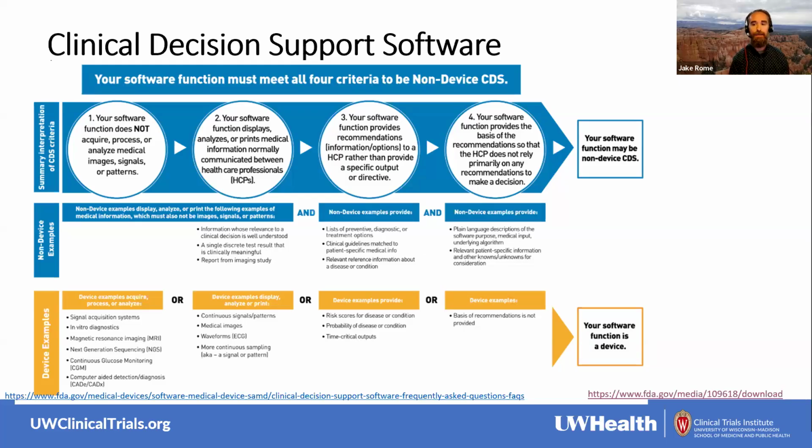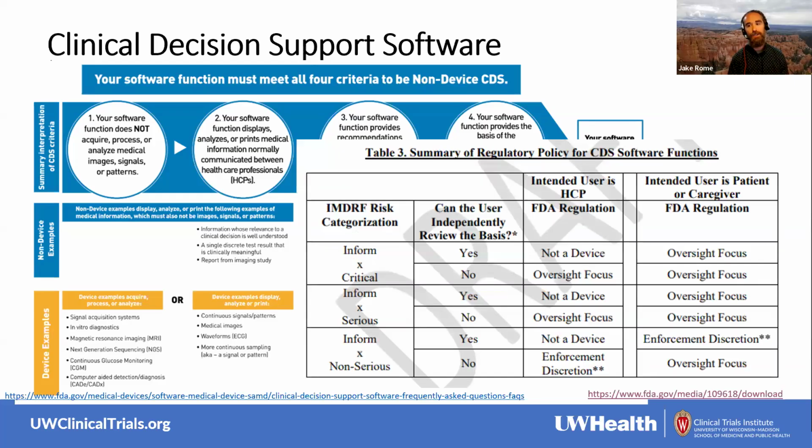But just a few notes, keep in mind that if you're analyzing images or signals, you're not going to qualify as what the FDA calls non-device CDS. It is going to be a medical device in the FDA's eyes. And also, if you're patient facing, if the device influences how a patient acts, then you're also not going to qualify as non-device CDS. That is something that the FDA is focused on in terms of regulating medical devices and software as a medical device.